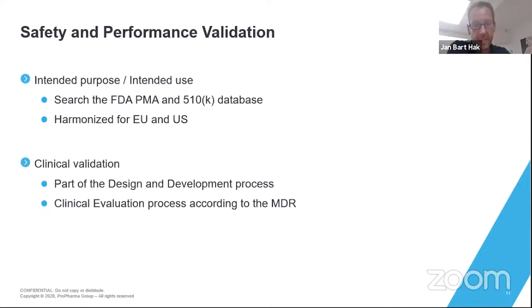Little sidestep on that. Clinical evidence, or clinical studies, is not necessarily the same as a clinical evaluation. Your clinical evaluation is a process that starts from the moment you start designing, and throughout your design process, you evaluate clinical data that you get from literature, from your own studies, from previous marketed devices, and obviously your own medical device. And at the end of the evaluation, you consider the safety and performance data, and you can conclude that it is okay to submit or that you have to conduct another clinical study. This is the start of your clinical development and your clinical validation.